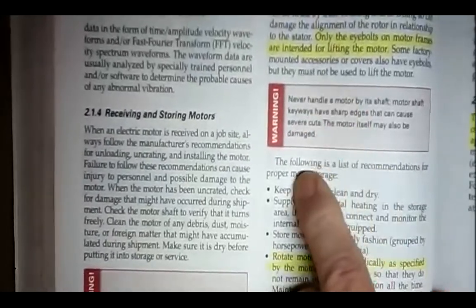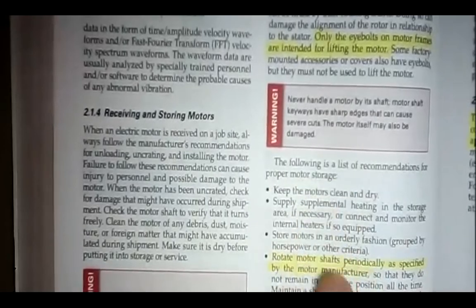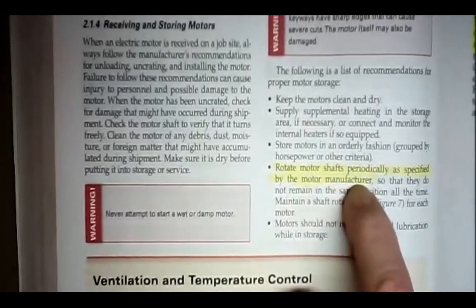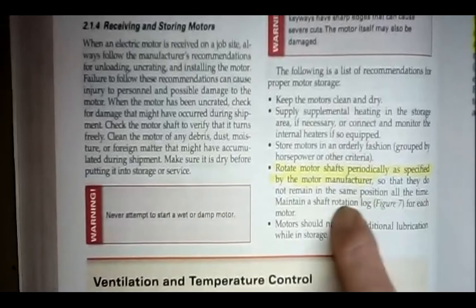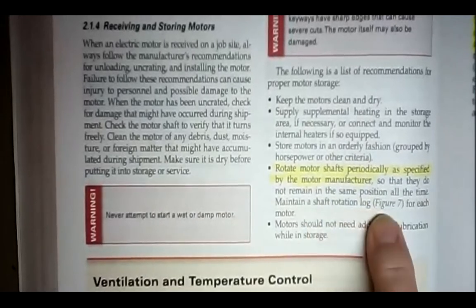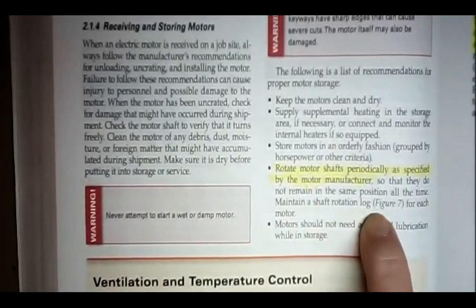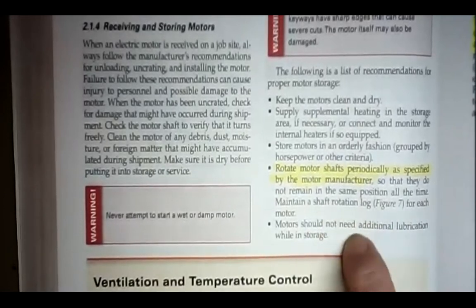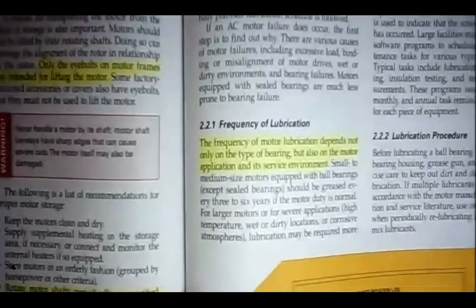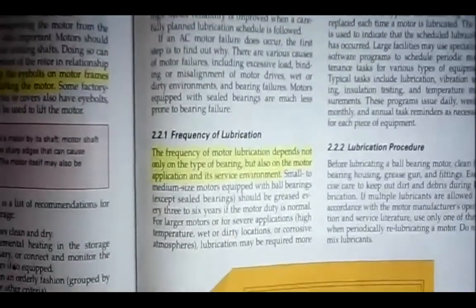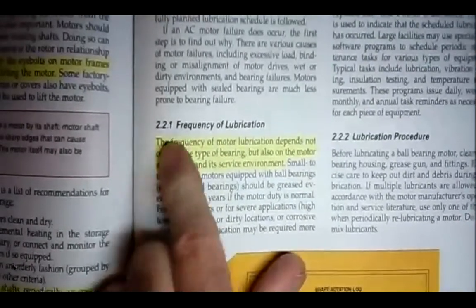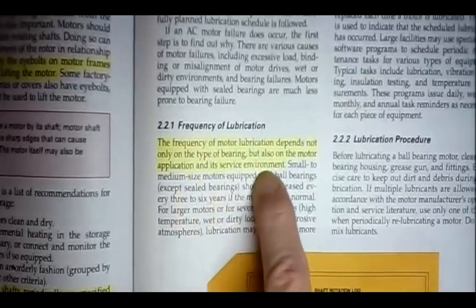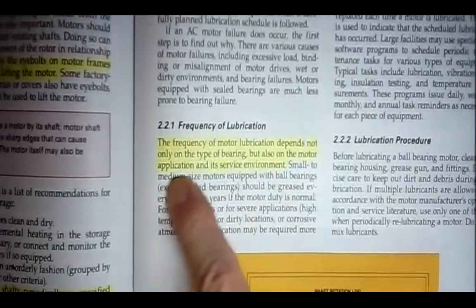This is if the motor is going to be stored for a long time. The following is a list of recommendations for proper motor storage. If you're going to store that motor for a long period of time, rotate the motor shaft periodically as specified by the motor manufacturer so that they do not remain in the same position all the time. At least once a week, you should go into the warehouse and rotate the armatures of those motors, especially if they're oil lubricated. It gets the oil into the bearings. It makes sure that they don't have any surface rust building up. Make sure that they can break free. Frequency of lubrication. The frequency of motor lubrication depends not only on the type of bearings, but also on the motor application and its service environment. Again, what is it doing and where is it doing it?